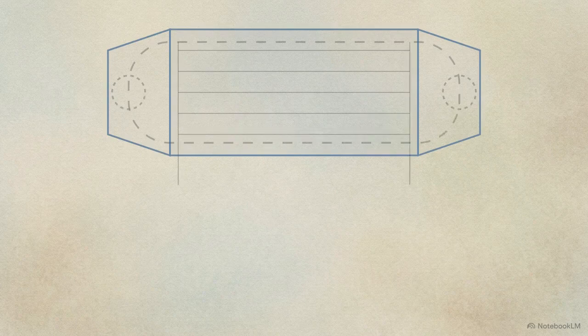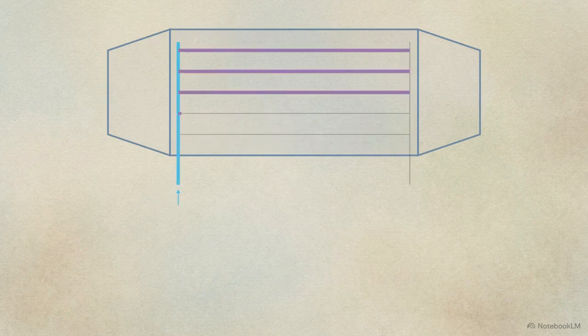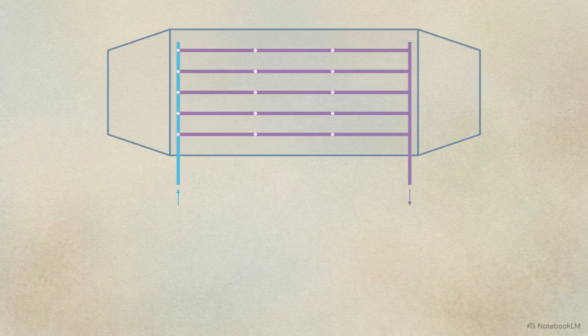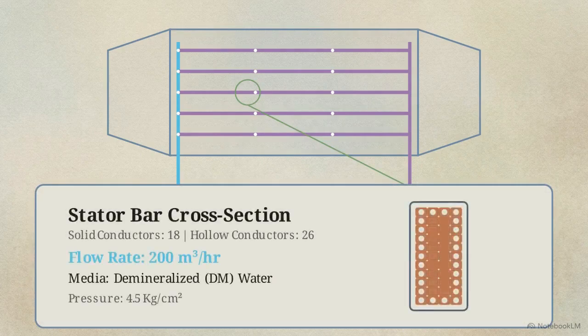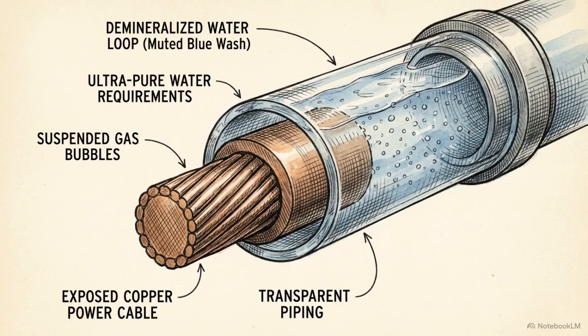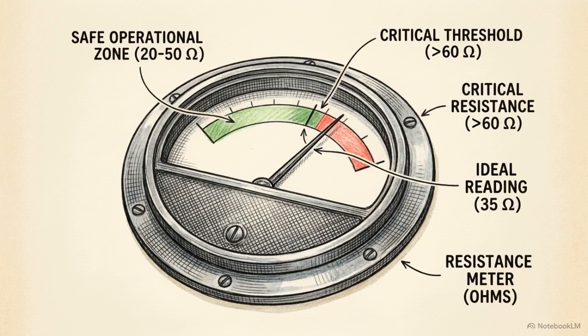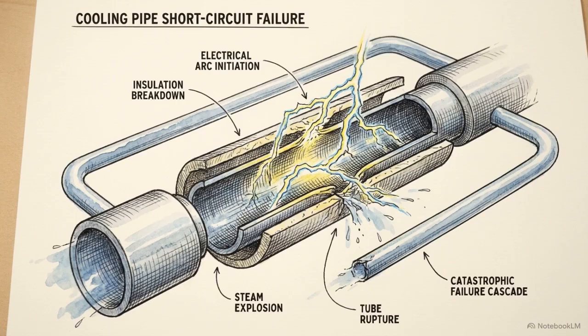Heat removal requires a trimodal cooling architecture. This schematic traces three independent fluid loops. The blue path tracks demineralized water flowing directly through the hollow copper stator conductors, circulating at 200 cubic meters per hour to strip heat from the slot internals. Because this water touches the live conductors, its purity is critical. The demineralized water must maintain a specific electrical resistance of at least 200 kiloohms per centimeter. If the resistance drops, the 24 kilovolt output would short-circuit straight through the cooling loop.